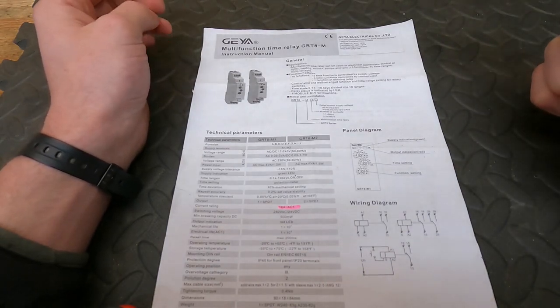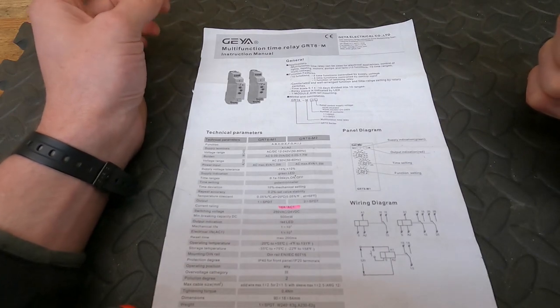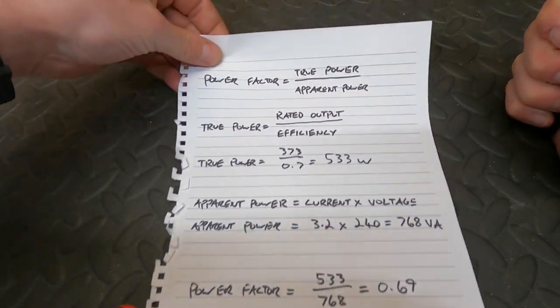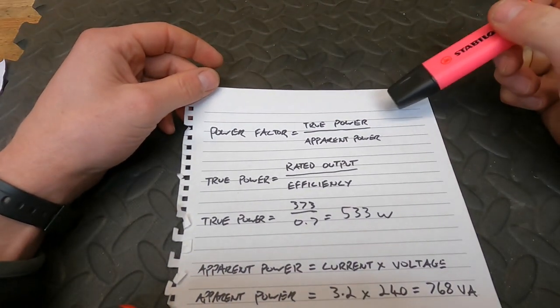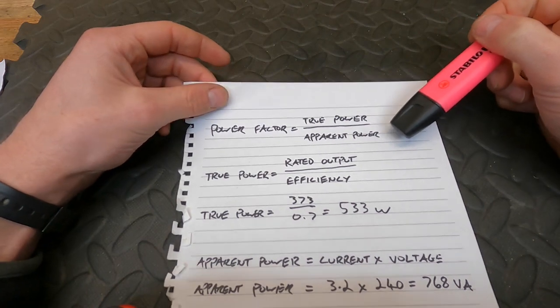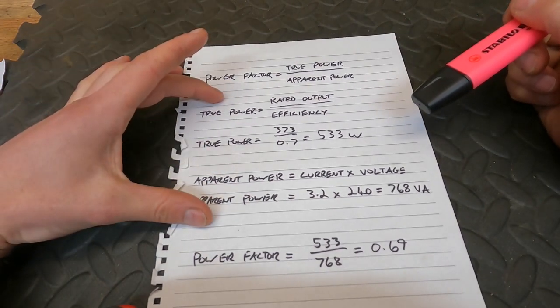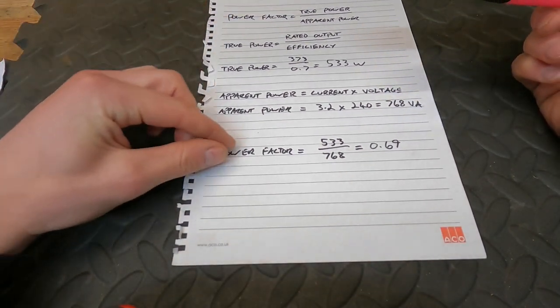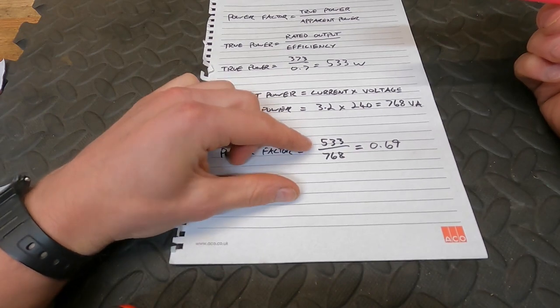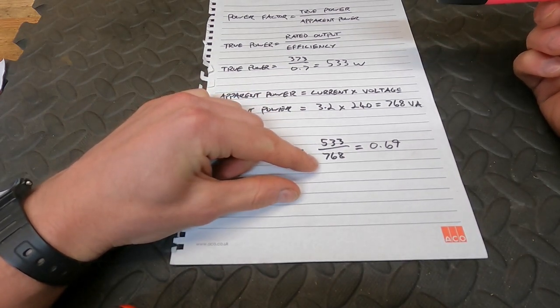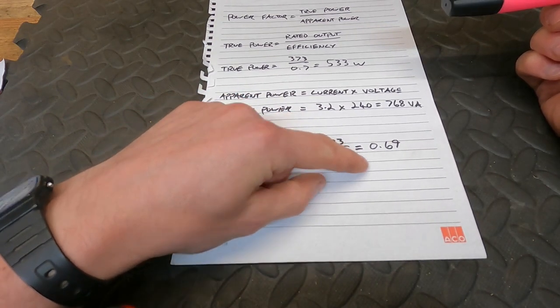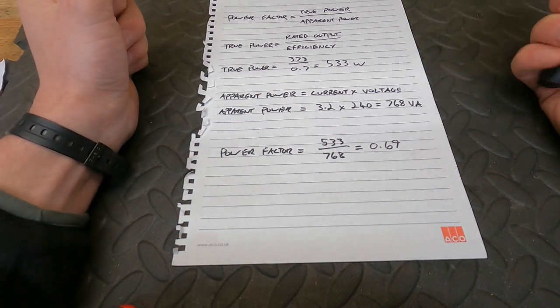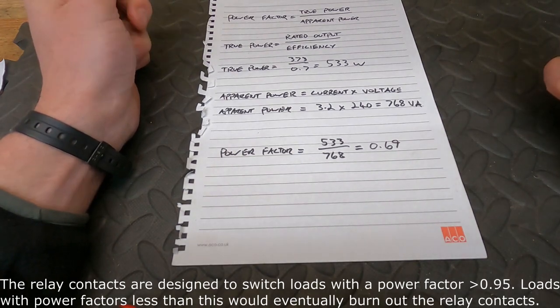We don't know what the power factor of the motor is because it's not on the nameplate, but we can work it out. The power factor is equal to the true power divided by the apparent power. This is all the working, which you can look at if you're interested. For this motor, the power factor is equal to 533 watts divided by 768 VA, which gives us a value of 0.69—well below the 0.95 value implied by the AC1 spec.